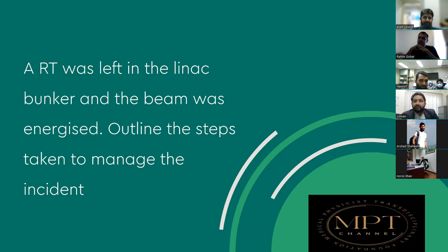First of all, we will report this incident to the radiation protection officer, and if the person is still inside the bunker and the beam is on, the first step should be to press the emergency button and turn off the beam, and then report to the radiation protection officer. He will take the radiation dose measurement equipment that the person is wearing, and he will list the radiation dose that he has received during that time. And it will, of course, be reported in the incidents log that we have been creating, and if he has received a higher dose, it shall be reported to authorities.